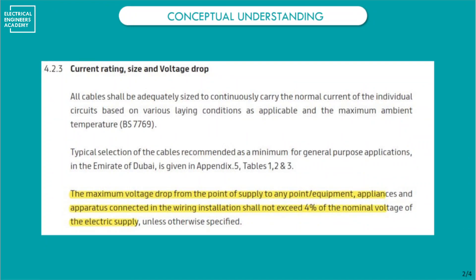What is our limitation for voltage drop? Referring to local regulations — DEWA in our case — section 4.2.3 states that the maximum voltage drop from the point of supply to any equipment, appliances, or apparatus connected in the wiring installation shall not exceed four percent of the nominal supply voltage. So the total voltage drop from the transformer low-voltage side to the final outlet or light fitting should be less than four percent.